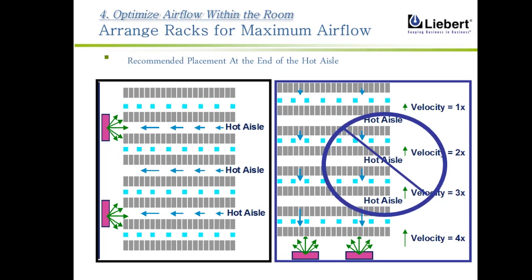This is one more interesting slide which shows the rack arrangement. If you look at the left side, the CRAC units are kept on the left side, 2 CRAC units. In a typical room scenario, this could be 2 or 4 CRAC units on either side of the room. In this slide, I have shown 2 CRAC units on the left side. So once I am using this cooling technology, the hot aisle is in front of the CRAC unit, and the cold aisle is at the side. So I am flowing the air from the cold aisle, and the return air is coming from the hot aisle at the top portion of the racks, and is again sucked in by the CRAC units.